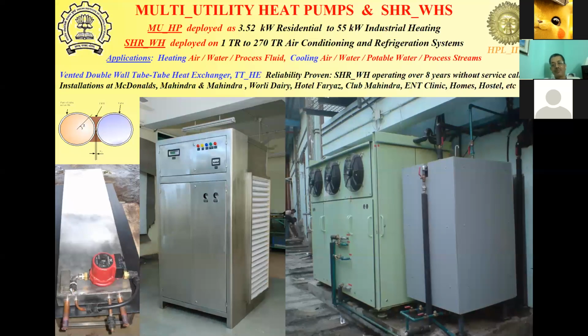And because the pressure is higher, it can condense at a higher temperature. And because of the superheat, the superheat is much higher than the condensing temperature. Typically, the condensing temperature for an air-cooled chiller or air-cooled refrigeration system for this application would be operating at 54.4 degrees for a 35-degree ambient, typical ambient in, say, Mumbai.